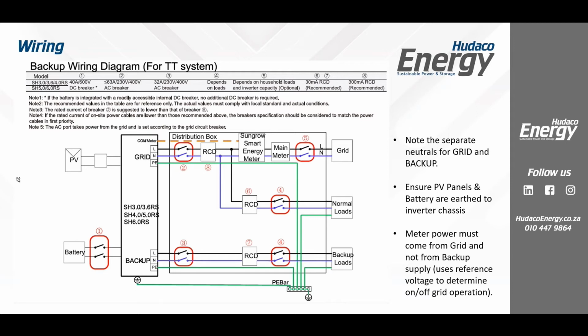Okay, this is really critical. Please use separate neutrals. Okay, we've seen quite a lot of sites. The first thing that happens is you start seeing lights flickering. The second thing that happens is the system's not providing the right amount of power because it's confusing neutrals between the two. When this drops, all of a sudden, are we floating? Are we where? So please make sure that you have separate neutrals on backup mode or on both grid and backup. Okay, really, really important. You can have common earth here, you know, your PE, but please look how the neutrals are separate.